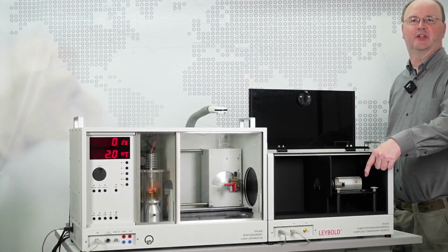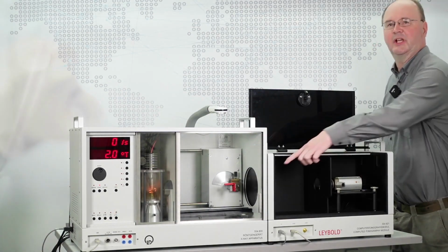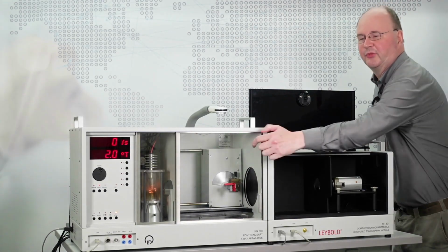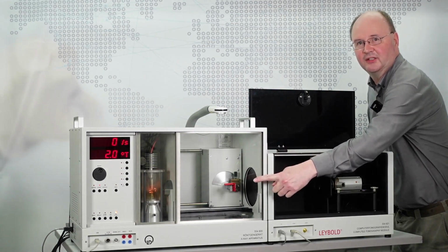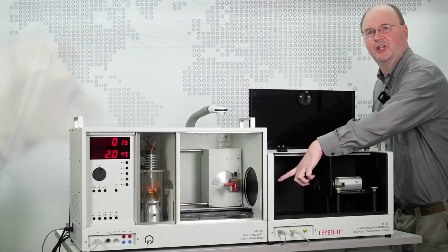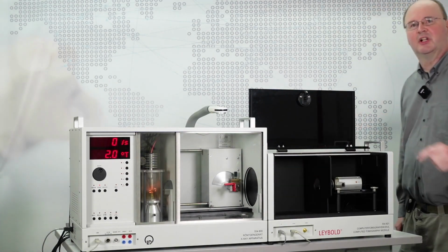And here we see our tomography module. The silvery thing here is a camera looking at the fluorescent screen from the outer side. So from the inside there are X-rays passing on the fluorescent screen. You see this black disc here. And from the other side, visible light is emitted wherever the X-rays pass.